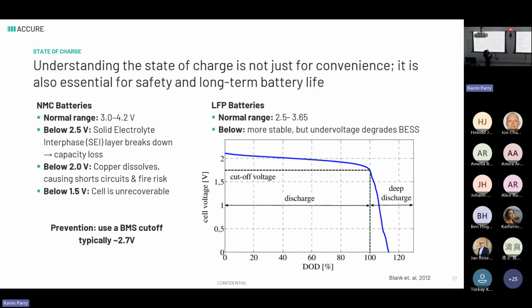For NMC batteries, which are one of the two main types currently used, NMC and LFP, I'll explain them a bit more in a bit. For NMC batteries, we see a normal range of 3 to 4.2 voltage. If we go below 2.5, the electrolyte interface breaks down, meaning the ability for the system to be reversible breaks down, and thus you have capacity loss.